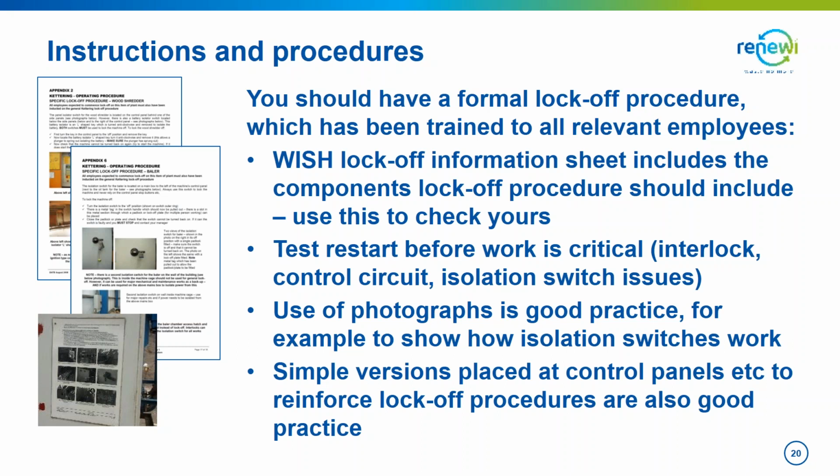The one thing I will linger on is restart. This is critical. When everything's locked off and you're all happy, try and start the machine again. Obviously, if it doesn't start, happy days, you've succeeded. But you'll be surprised how often everybody's locked off, they try to start the machine up, and it does start. So a test restart is critical.